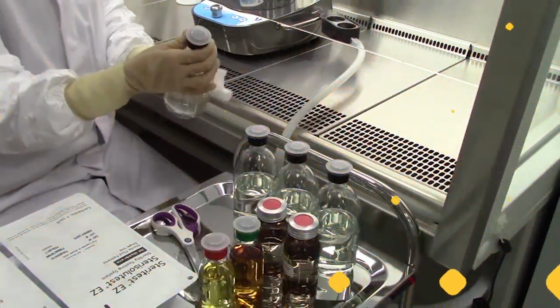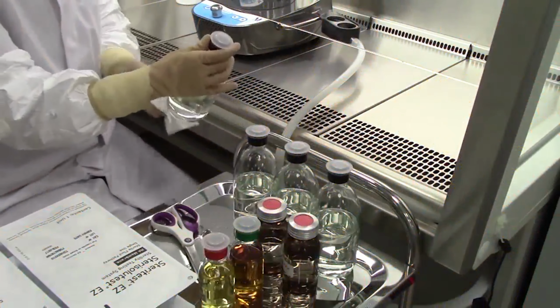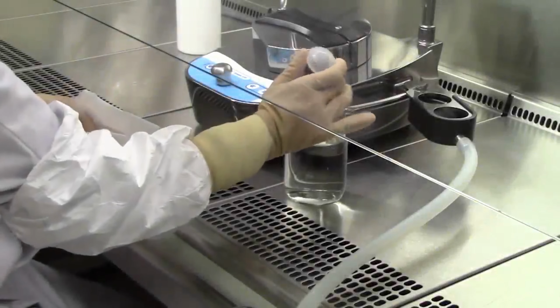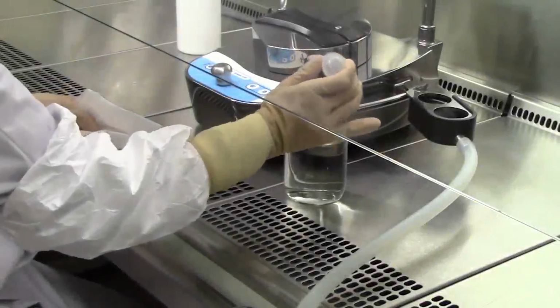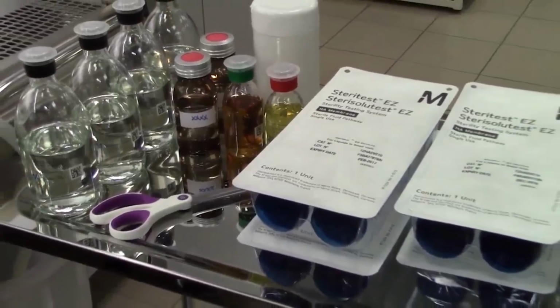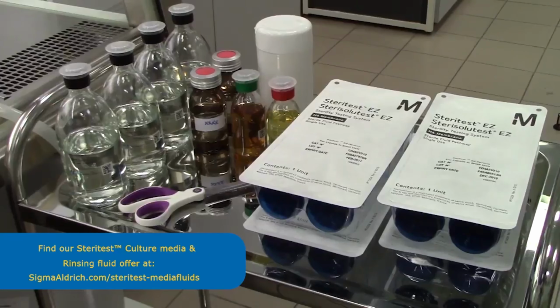All material needed should be decontaminated before being introduced into the laminar flow hood. Remove all plastic covers from bottles and sanitize the lids. You will need the Steritest Symbio pump under the LFH, Steritest EZ devices, fluids for pre-wetting and rinsing according to the SOP, and the sample, whose volume and quantity are determined according to the Pharmacopoeia and specified in the SOP. You will also need tryptic soy broth for aerobic bacteria, yeast and molds, thioglycolate for anaerobic bacteria, scissors, and surface decontamination wipes.